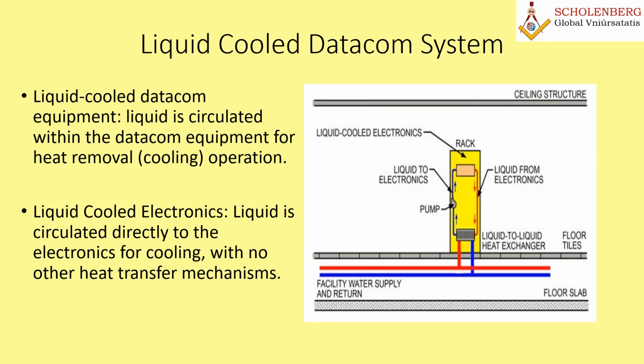In the liquid cooled rack, a circulated liquid provides heat removal, that is cooling, at a rack or cabinet level for operation. For example, it includes rear door or in-rack heat exchangers that transfer a large percentage of datacom equipment waste heat from air to liquid. The second one is liquid cooled datacom equipment. The liquid is circulated within the datacom equipment for heat removal operation. This is more common in fact.